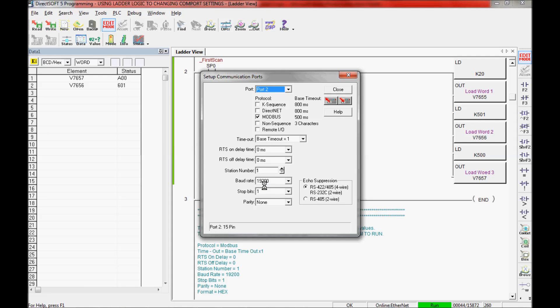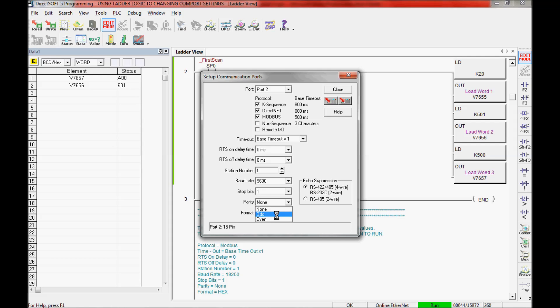You can see that my COM port right now is set up for a baud rate of 19.2. The protocol is Modbus and the parity is none. I'm going to change this back to the factory default settings. These settings don't get changed if you clear the PLC memory, but they will be changed back to factory default if you initialize the scratch pad. I highly recommend initializing the scratch pad when you clear programs off your processor, as it will automatically put any written V-memory locations back to zero.